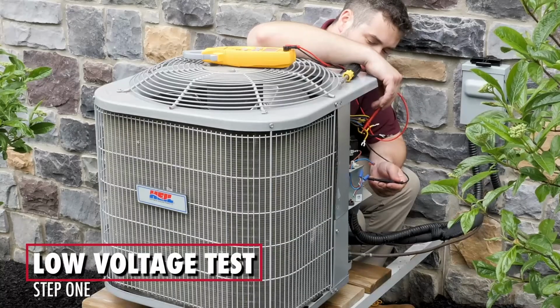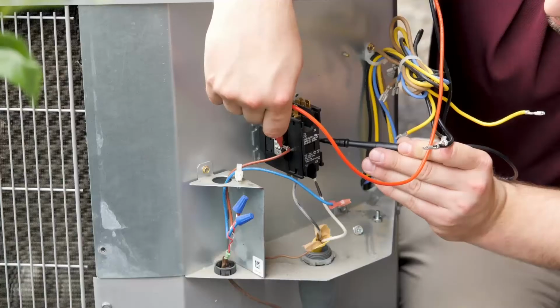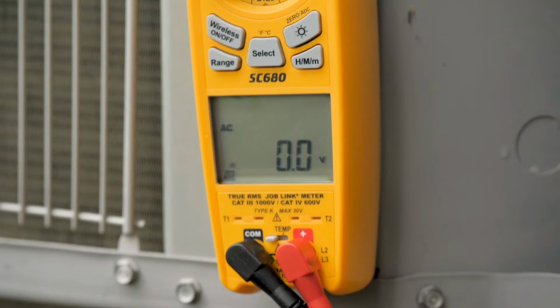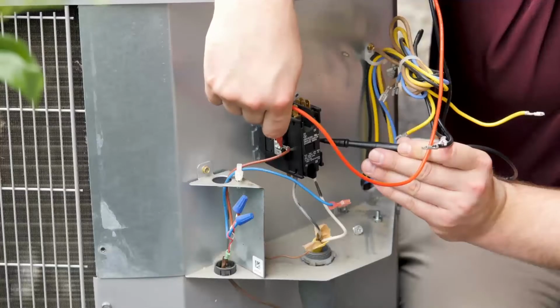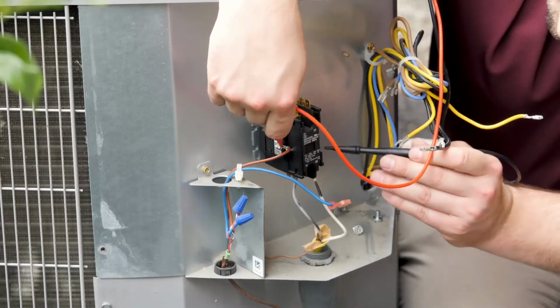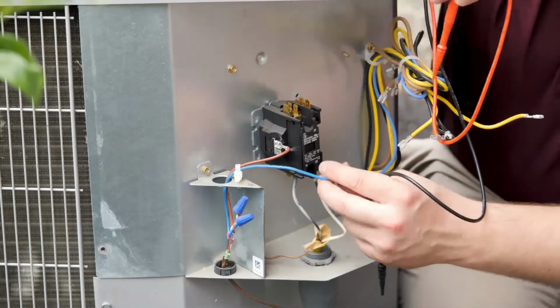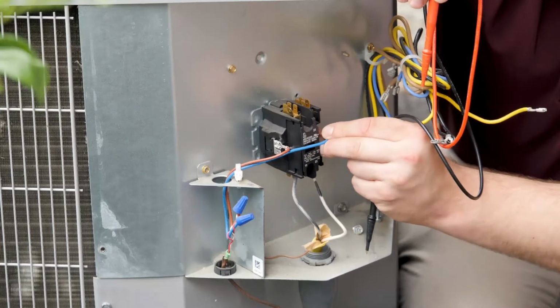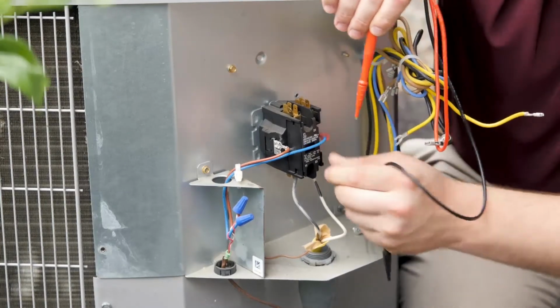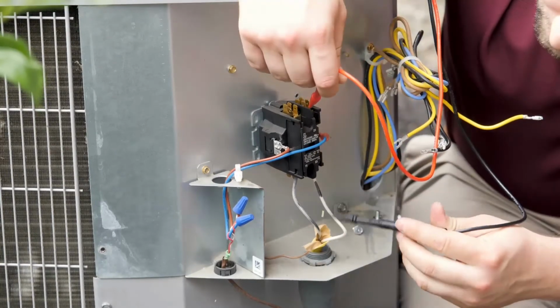We're going to test the contactors. And first we're going to look for 24 volts. We have it disconnected, so obviously we won't find any 24 volts right now. Justin's going to move the wire into position, which will close the contactor. Because we heard the contactor close, we know we have applied control voltage across the coil.